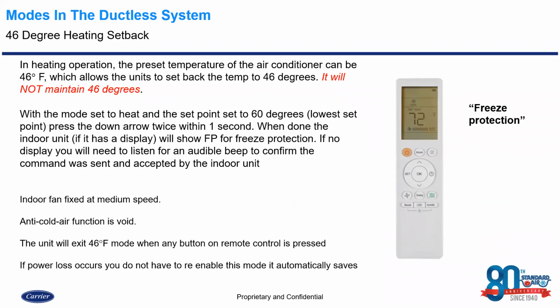Next feature we're going to talk about is our 46-degree heating setback. Okay, so this is also known as FP or freeze protection. With this freeze protection, we're going to go in the heating mode, obviously, because this is the only mode that it's applicable in. Once we're in the heating mode, we're going to turn the set point down to its lowest set point that it can go, 60 degrees. Once we've gotten to 60 degrees, we're then going to go ahead and press the down arrow twice within 1 second to be able to initiate this setback on there.